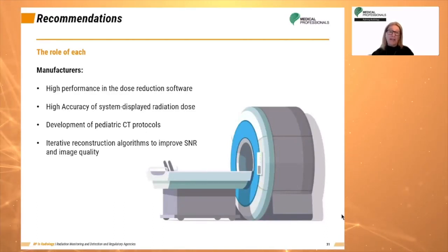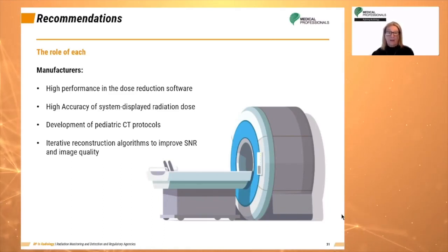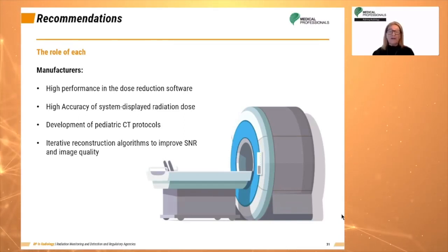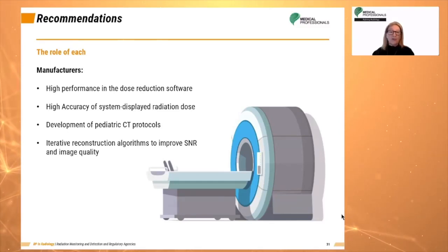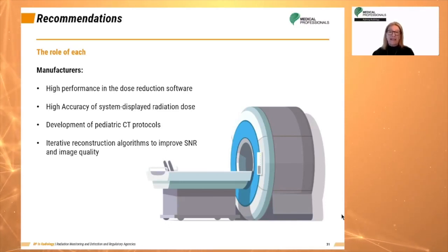Manufacturers have an obligation to ensure certain parameters, including high-performance dose reduction software, high accuracy of displayed radiation dose, iterative reconstruction algorithms to improve signal-to-noise ratio and image quality, and the development of pediatric CT scanning protocols.